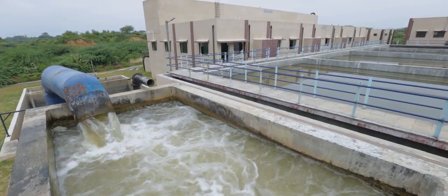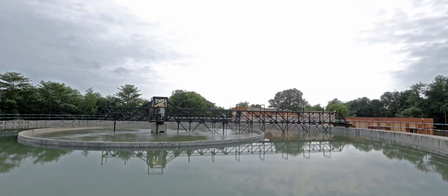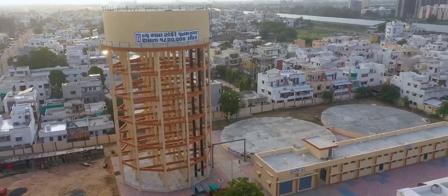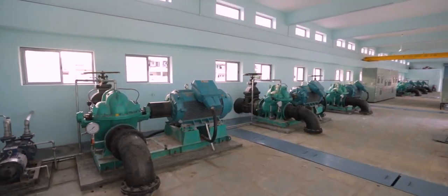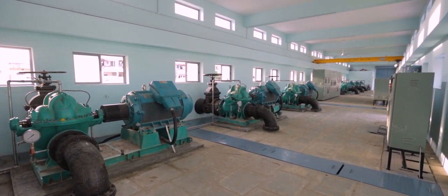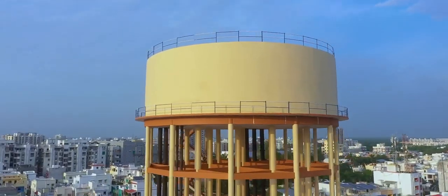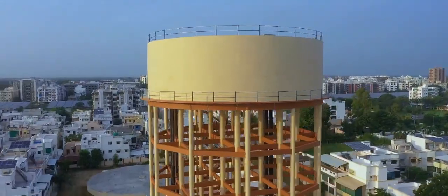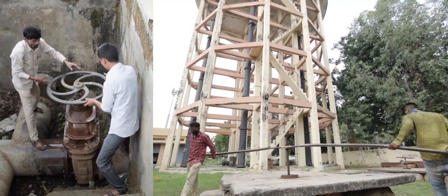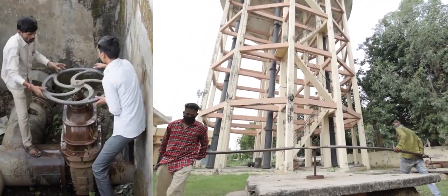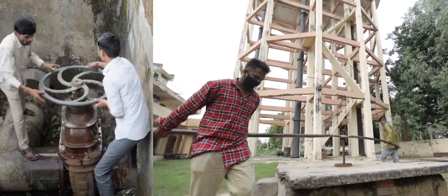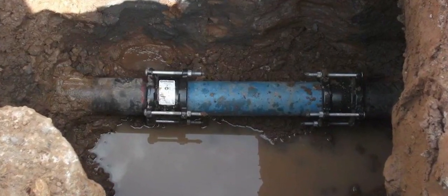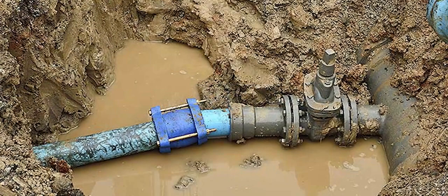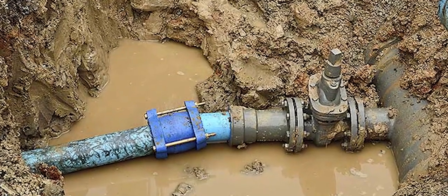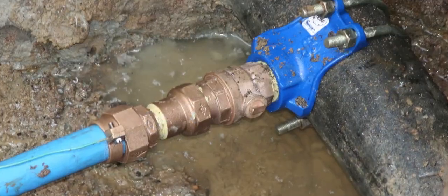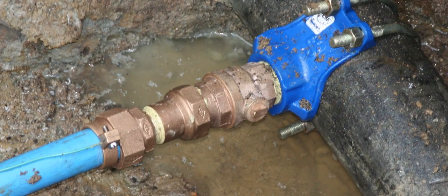The treated water is distributed across the city in all 4 zones through 30 overhead tanks and 22 booster pump houses. Distribution from overhead tanks into the water supply network is done manually by field operators on the basis of thumb rules. Currently, there is no method of detecting leakages and tracking and measuring UFW, that is unaccounted flow of water, in the water supply network.